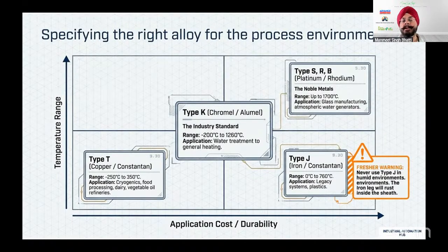Second, we have the type K, where we use chromel and alumel. This is the most used in the industry because it has a range from minus 200 degrees to 1260 degrees. If you go into a freezing application, normally we have minus 40 or minus 50 degrees and the thermocouple works. We have hot treatment applications at 800, 900, 950 degrees, and we still have the same thermocouple. So from minus 200 to 1260, it caters to almost 70 to 80% of the industry. So mostly you will find people using K type in the industry.